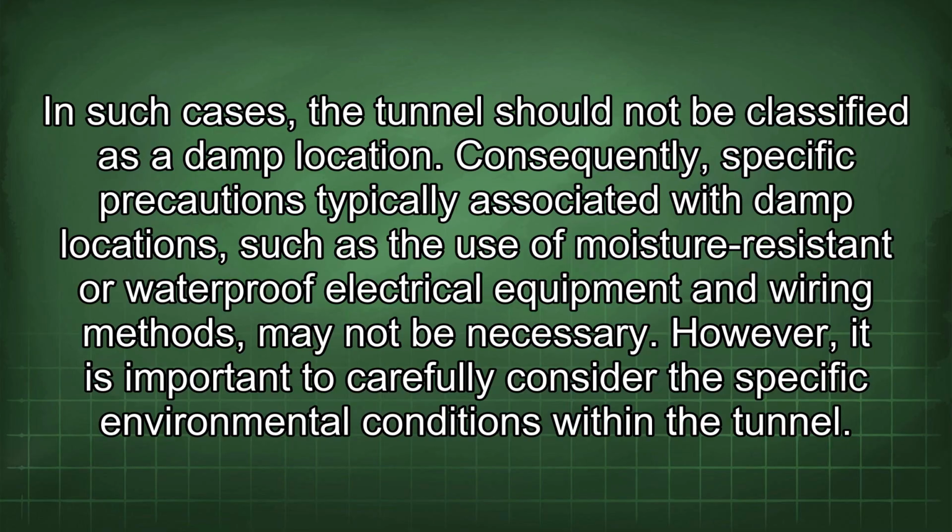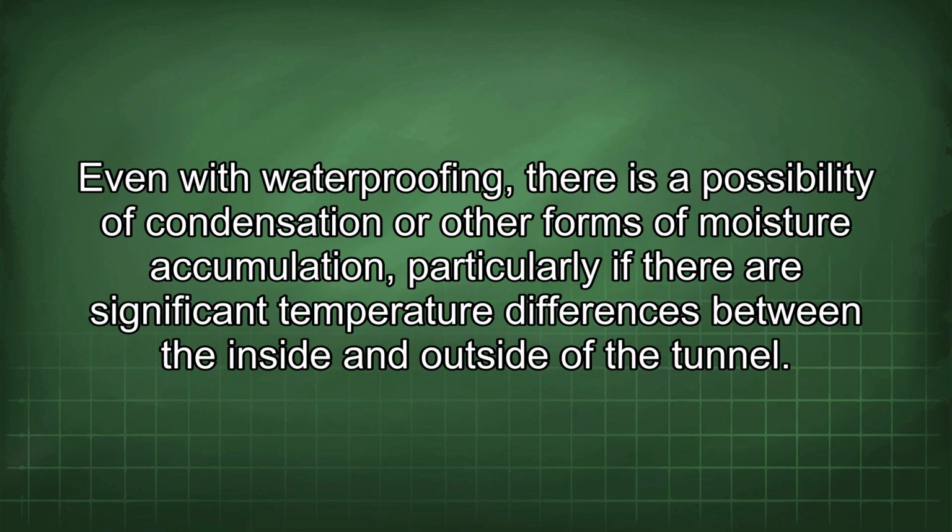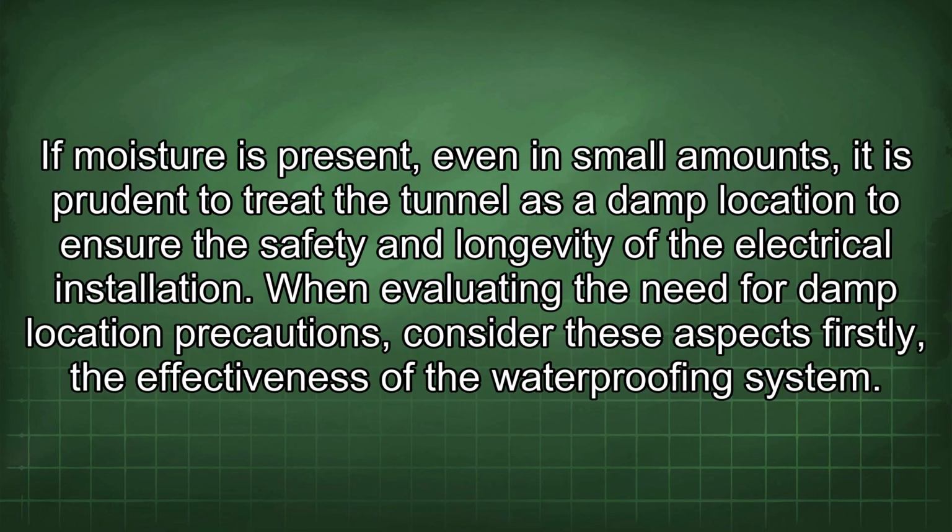However, it is important to carefully consider the specific environmental conditions within the tunnel. Even with waterproofing, there is a possibility of condensation or other forms of moisture accumulation, particularly if there are significant temperature differences between the inside and outside of the tunnel. If moisture is present, even in small amounts, it is prudent to treat the tunnel as a damp location to ensure the safety and longevity of the electrical installation.